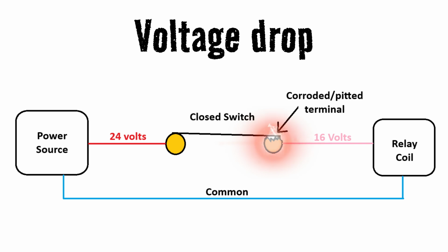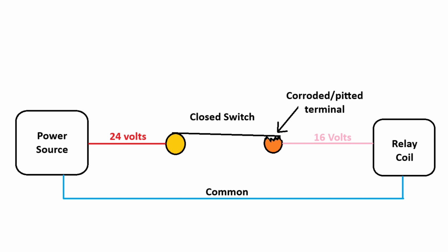Now, this is another reason why I don't particularly like using ground as a reference point, because again, this is another situation where it's very difficult to tell the difference between an improperly grounded circuit or you're actually experiencing a voltage drop. So I always like to use common or a neutral as a first choice, and then you can always use ground as a verification.